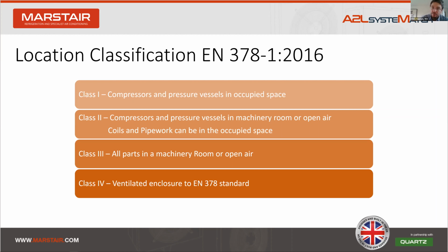So where does this leave us with the maximum charge? Well, within general access there are 2 categories: human comfort, which is for air conditioning, and other applications, which is obviously for refrigeration, which is where we are for cold rooms. When you work your way through the table, this gives us the limit relative to room size of 20% times the LFL times the room volume. We're also given an overall maximum charge limit, which calculates to 39 times the LFL. There is an alternative classification allowed, but this is for multi-splits, i.e. for multiple cabinets in a shop on the shop floor. So this can't be used for what we're looking at, which is single split cold rooms.